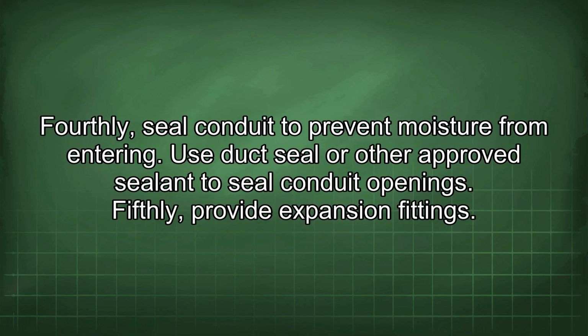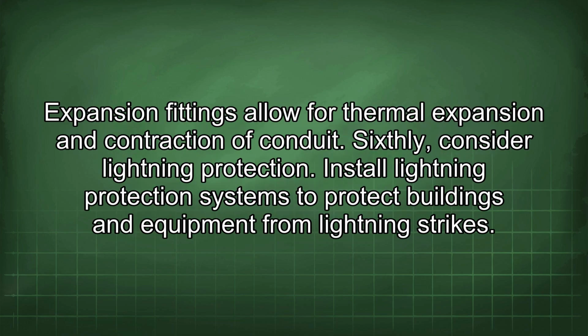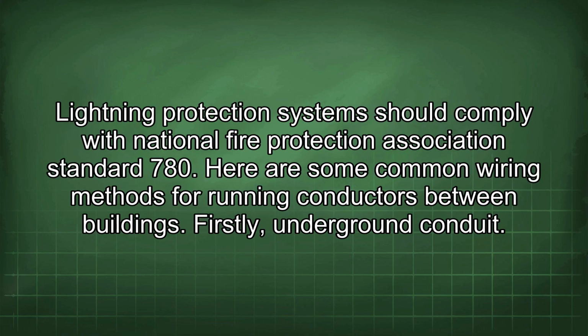Fourthly, seal conduit to prevent moisture from entering. Use duct seal or other approved sealant to seal conduit openings. Fifthly, provide expansion fittings. Expansion fittings allow for thermal expansion and contraction of conduit. Sixthly, consider lightning protection. Install lightning protection systems to protect buildings and equipment from lightning strikes. Lightning protection systems should comply with National Fire Protection Association Standard 780.